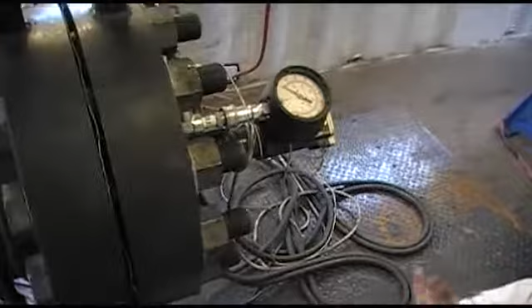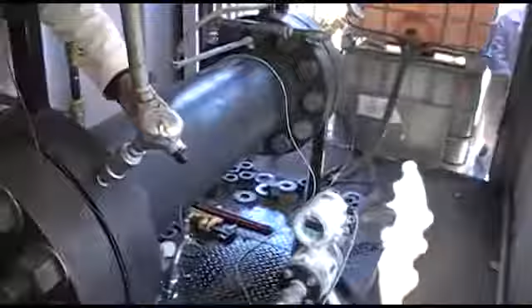The electrodes are controlled by this motor at the end, and that controls the position of the electrodes inside. This is the stepper motor for the completely automated control of the arc. These are the DC power input cables and either gas or air input valves, pressure transducers and other control equipment. All the plumbing you see around it is just for the water flow.